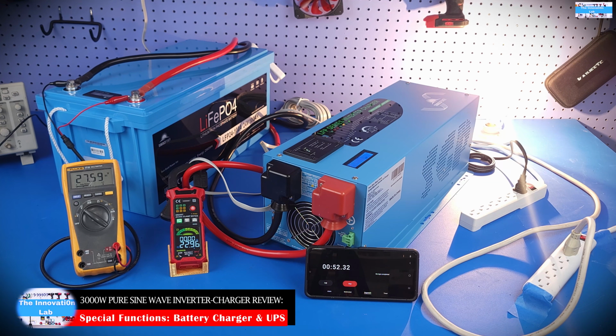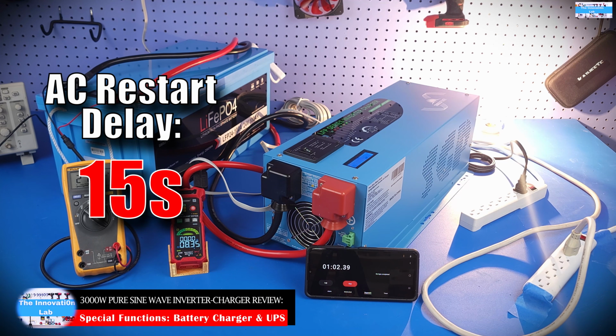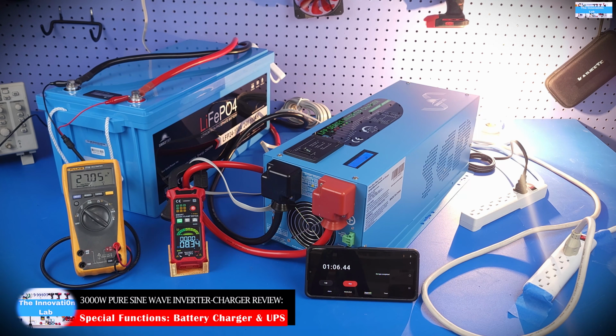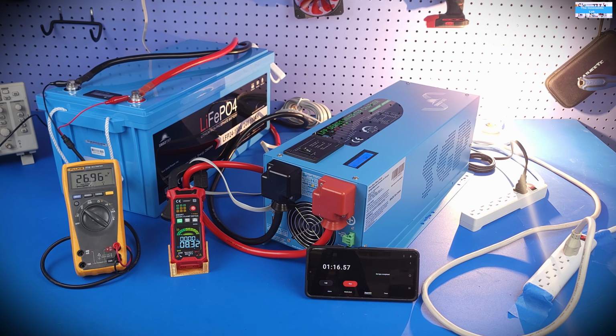So this is kind of a visual test and a time test. Whenever there is a power handshake, you can almost see the 10 millisecond flicker on our load. Also for this function, there is a 15-second delay for AC power coming in, meaning every time there's a reset or restart of the input AC power, the power inverter knows to wait 15 seconds before it switches the load to the incoming AC power.